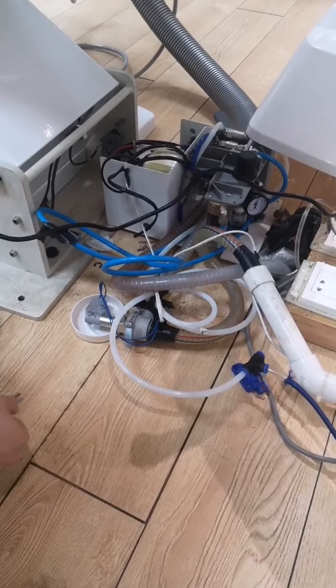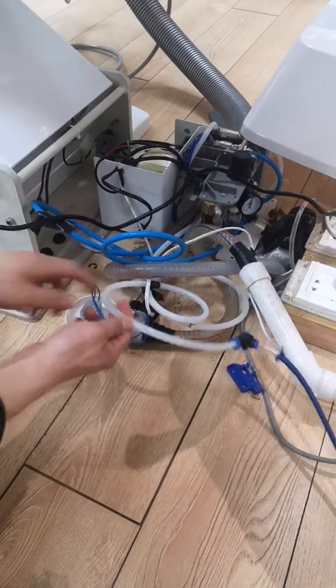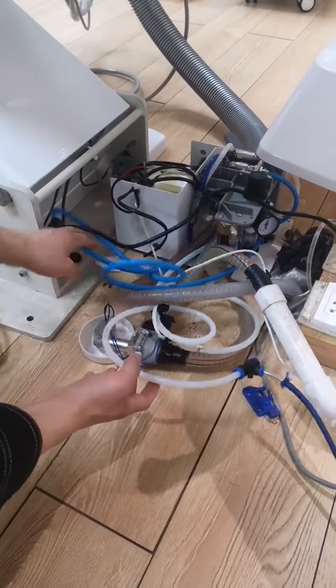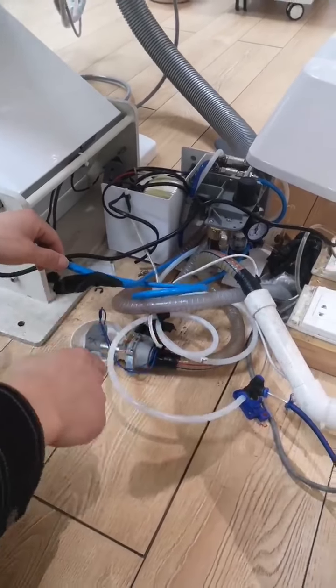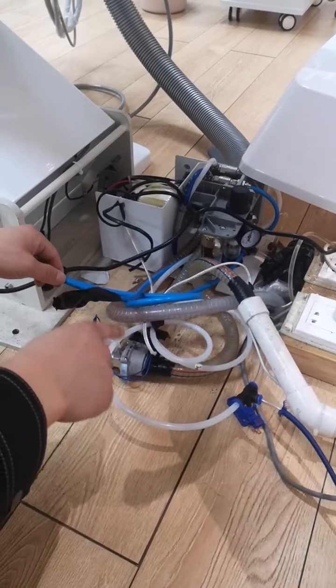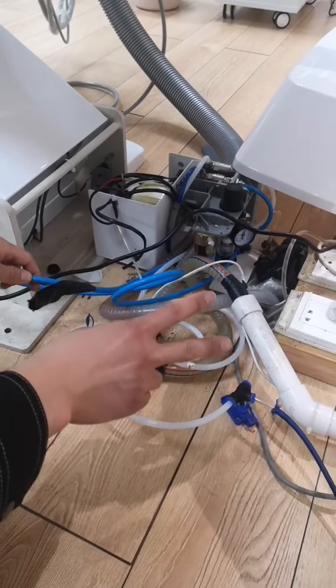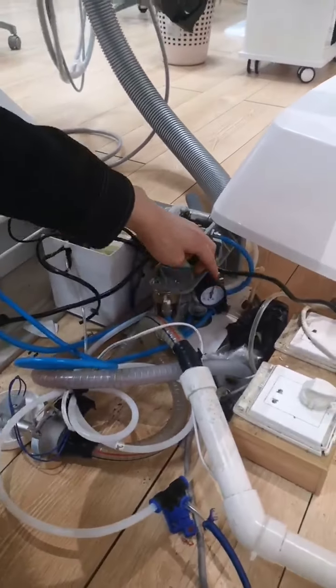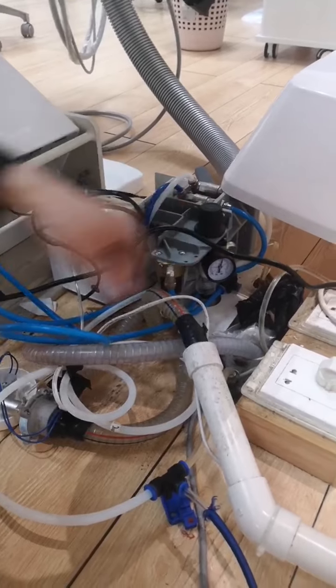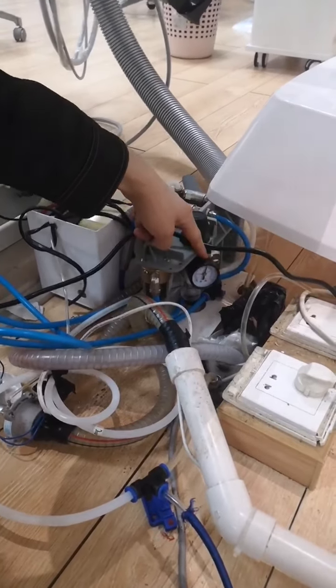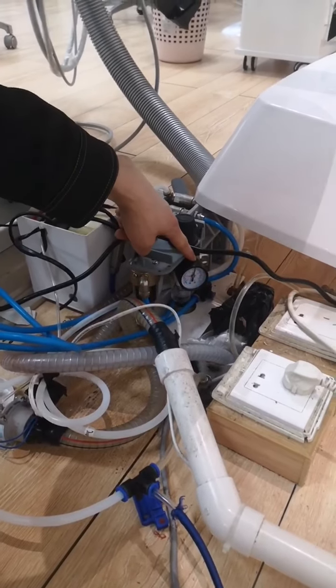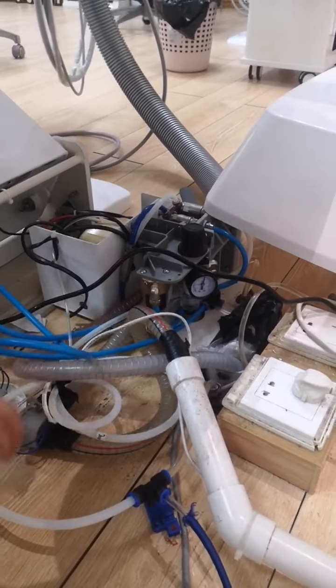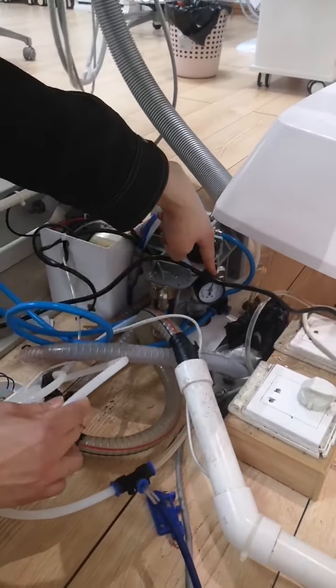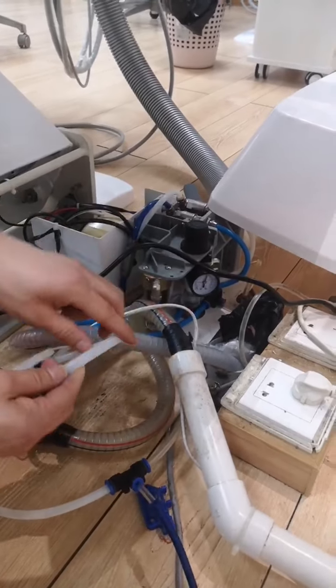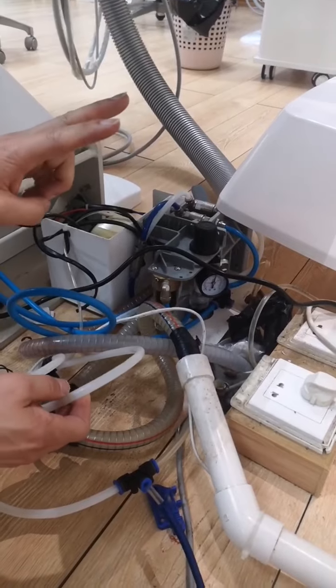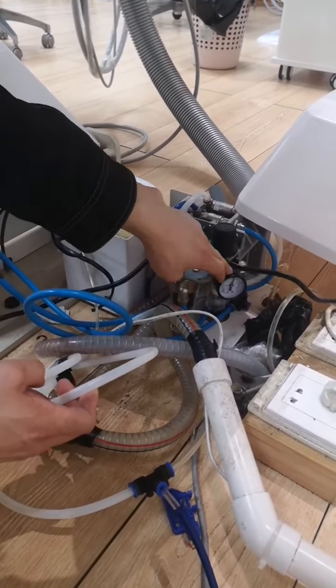We have three ways. The first way is that usually the air pipe is transparent in color, and the water pipe is blue. So we can distinguish the air pipe from the water pipe by color. That's the first way. The second way is that here we can see this is the air pressure gauge. Any pipe which goes through the air pressure gauge, or which connects with the air pressure gauge, is an air pipe. So we can check here, this kind of pipe goes through the air pressure gauge, so this kind of pipe is an air pipe. That's the second way.